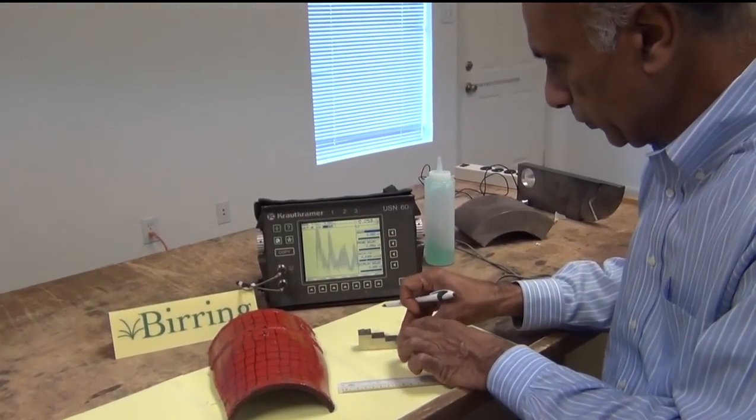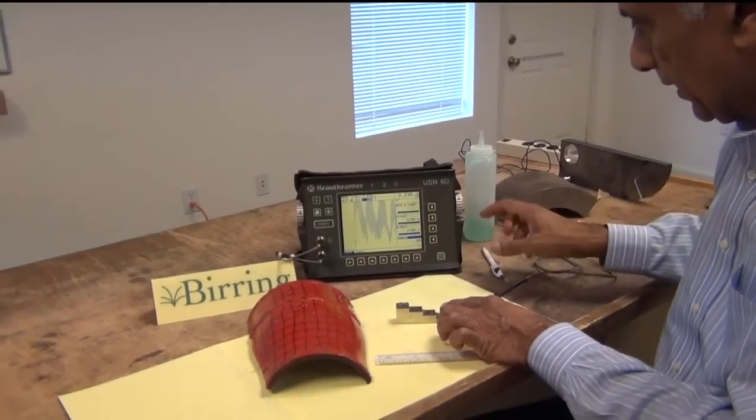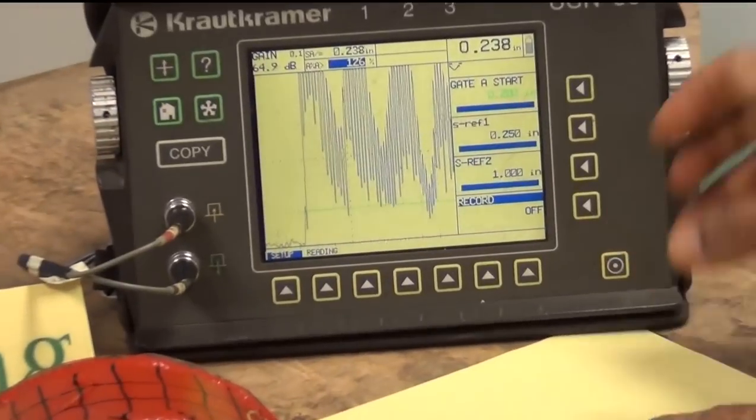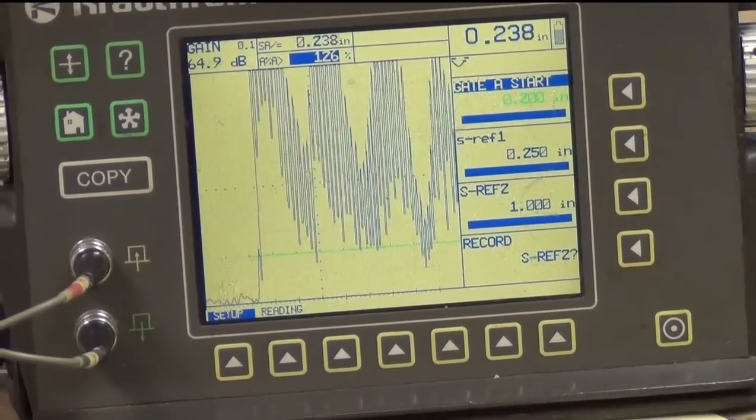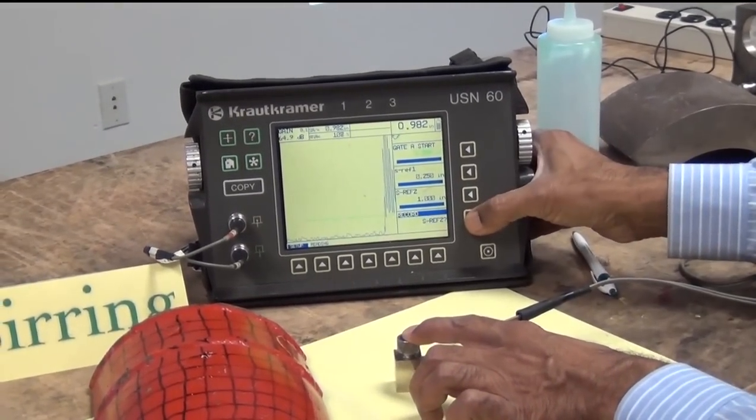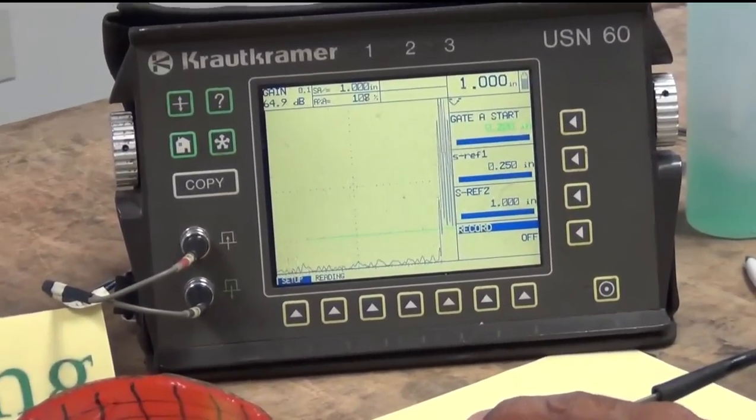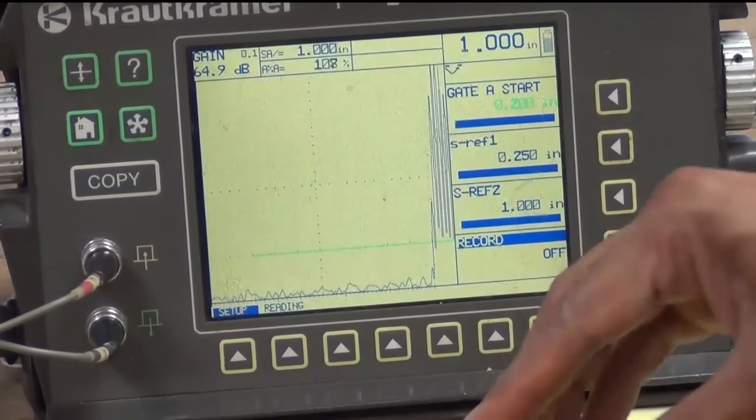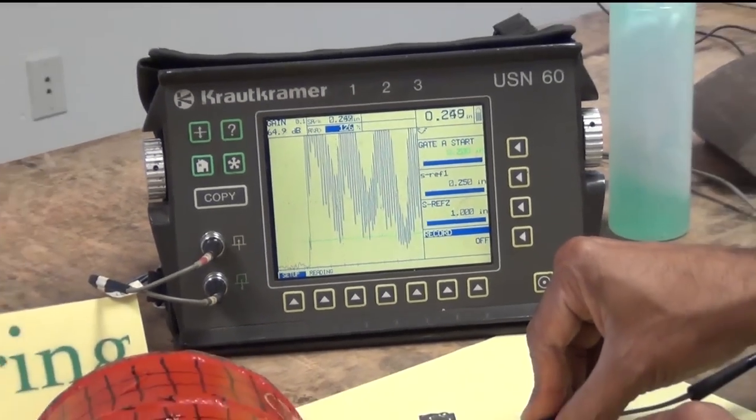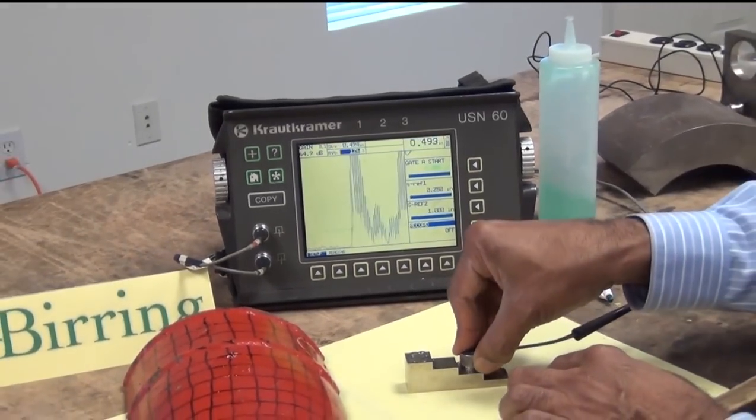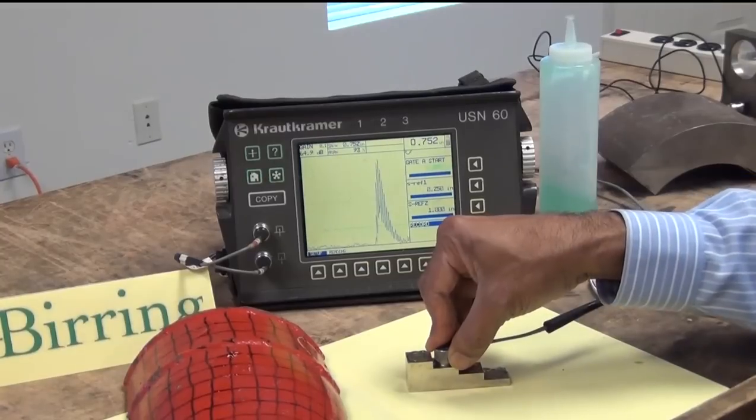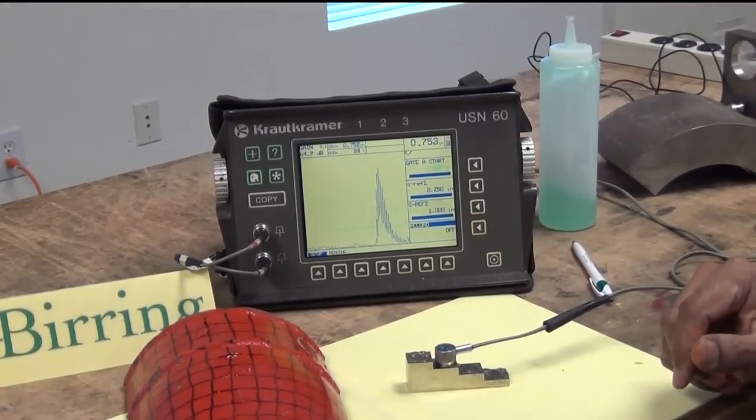Okay here we go. I will go to AutoCal. S reference 1 is 250. We will record S reference 1 now. S reference 2 is 1 inch here. Record it and now we are done. So now 1 inch is 1 inch. 0.25 inches is 0.25 inches or close within 1 mil. This is 0.5. This is 0.750 which is reading 752. So that completes our calibration.